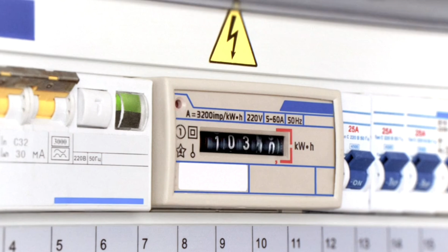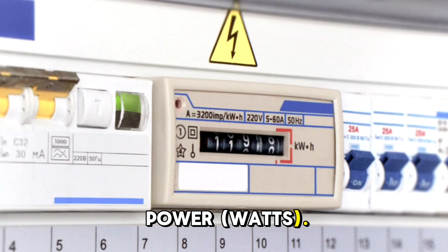Lower current for the same power. Because the voltage is higher, electrical devices operating on 220 to 240 volts draw less current, measured in amps, to produce the same amount of power in watts. For example, a 2000 watt appliance would draw about 9 amps at 220 volts: 2000 watts divided by 220 volts equals 9.09 amps. It would draw about 18 amps at 110 volts: 2000 watts divided by 110 volts equals 18.18 amps. Lower current means smaller and cheaper wiring can be used to transmit electricity, as wires with a higher current capacity tend to be thicker and more expensive.